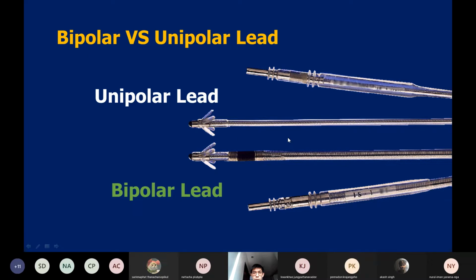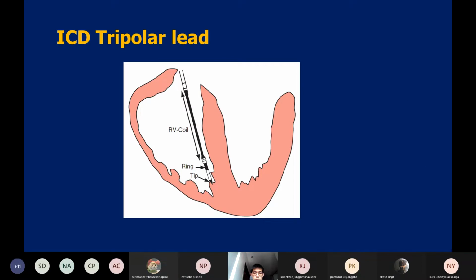This is the picture of both the unipolar and the bipolar leads. And this is the tripolar lead of the ICD. You can see that you have the tip and the ring, as a cathode and anode, and the RV coil can be another electrode if you want to use it. But we don't usually use this one, because we have these two electrodes already, and we use the bipolar instead of the tripolar lead.